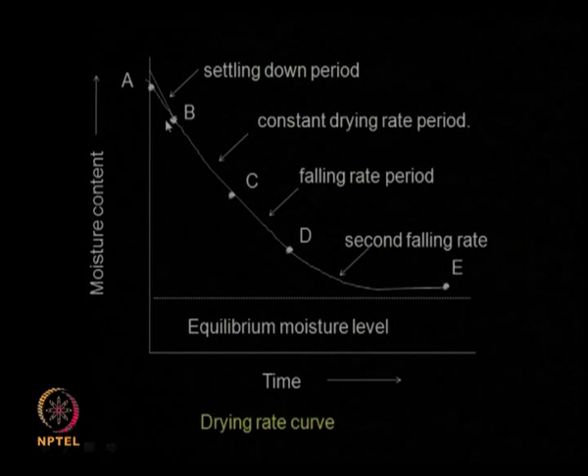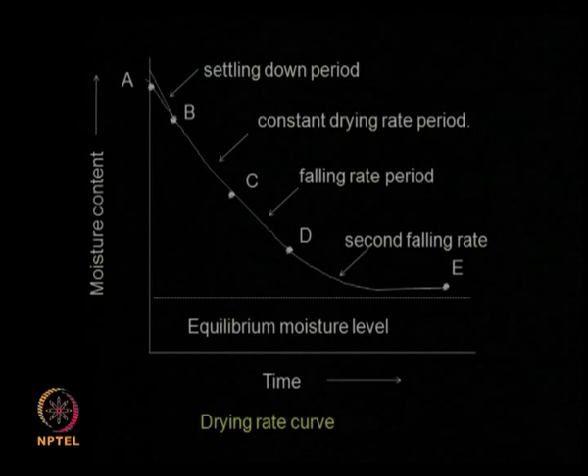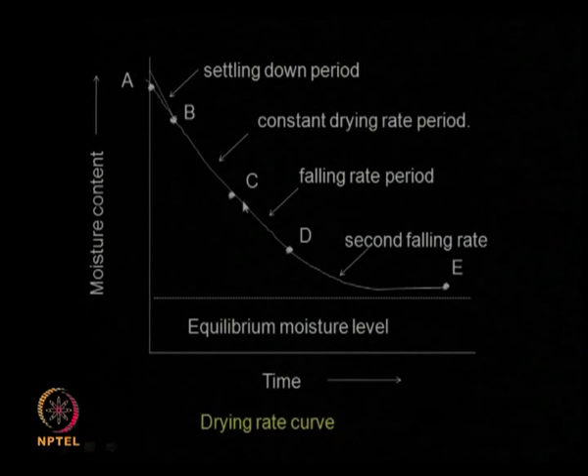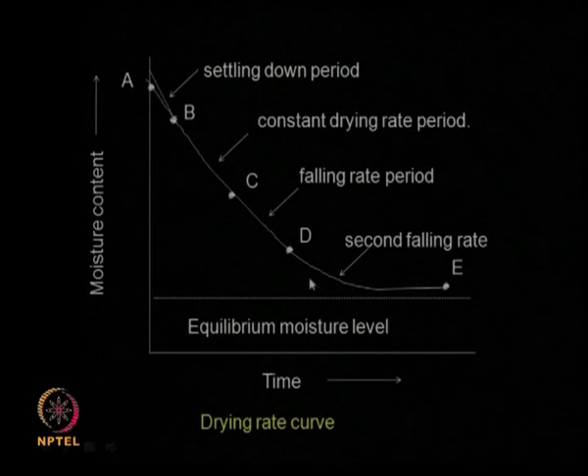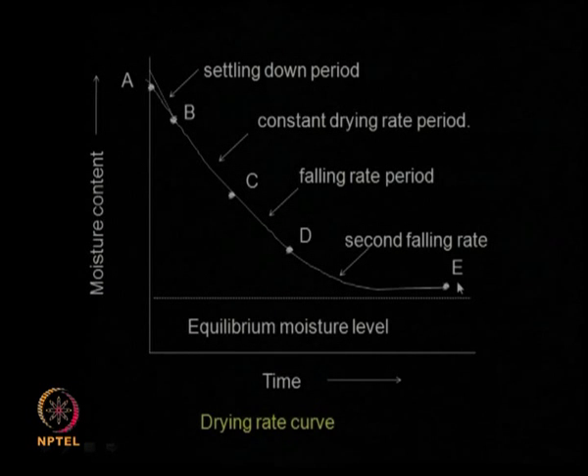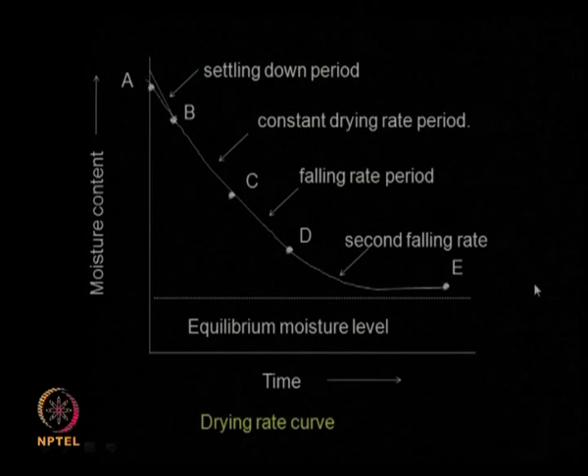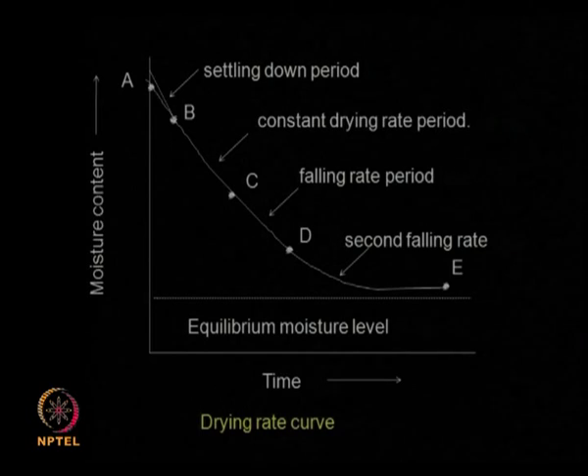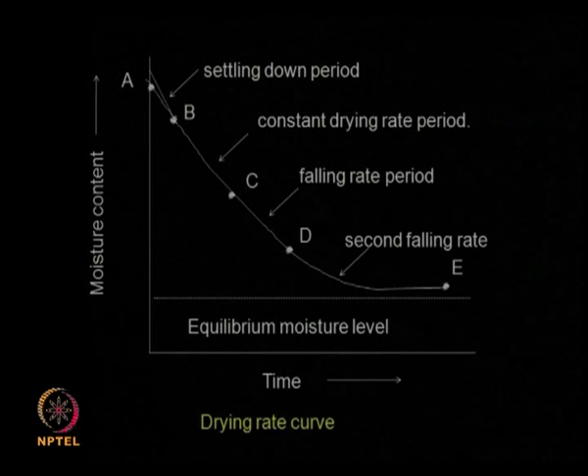When designing a dryer and calculating drying time, you have two periods: the constant drying rate period and the falling rate period. As drying continues, the material cannot give up moisture after some point — this is the equilibrium moisture content, which depends on the percentage relative humidity as well as the type of material (how hygroscopic it is, how porous it is). For example, leather has a higher equilibrium moisture content than soap. The moisture content finally settles down to the equilibrium moisture content — this is the drying rate curve.